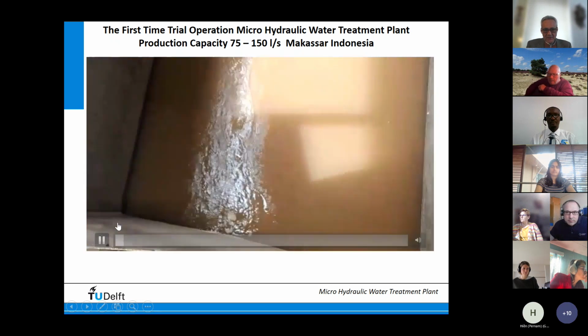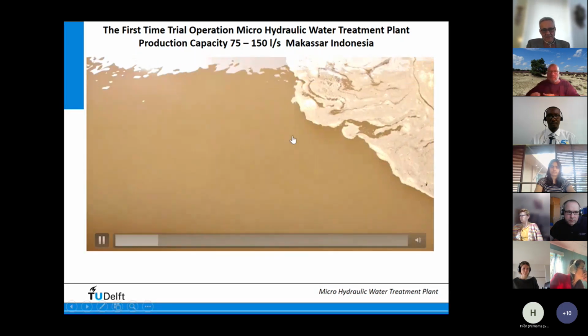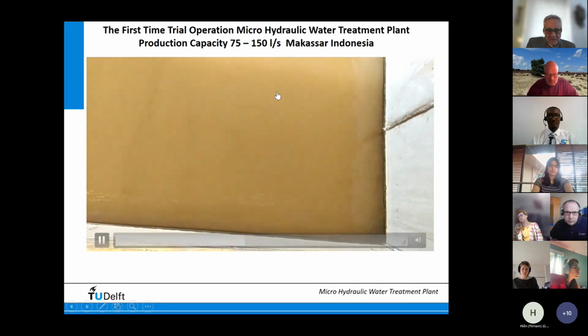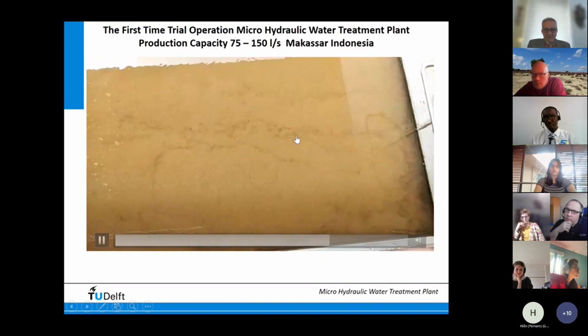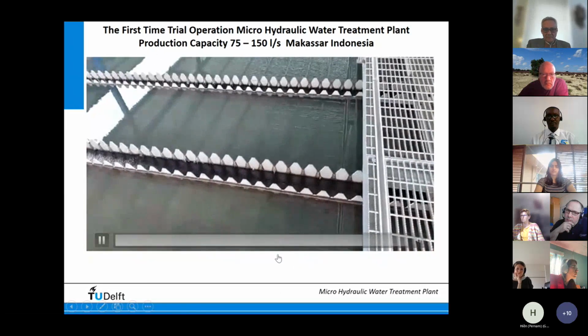This is a video I want to show you. We have 5 or 6 chambers of coagulation and flocculation. This is chamber number 1, and you can see chamber number 1 and number 2, and this is number 3. This is number 4. This is the final flocculation. You can see the flock is really gentle and very good, and it goes to the clarifier.